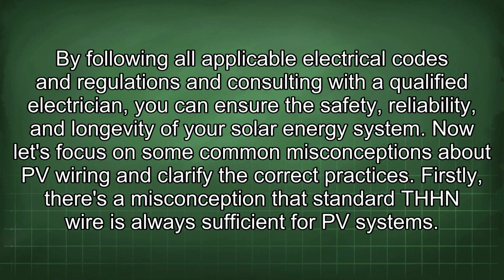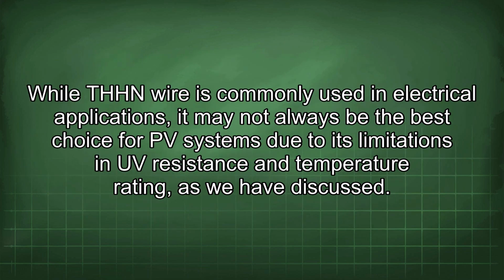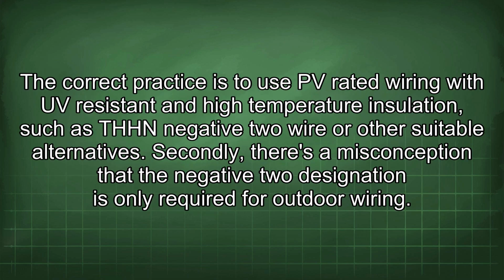Now let's focus on some common misconceptions about PV wiring and clarify the correct practices. Firstly, there's a misconception that standard THHN wire is always sufficient for PV systems. While THHN wire is commonly used in electrical applications, it may not always be the best choice for PV systems due to its limitations in UV resistance and temperature rating, as we have discussed.